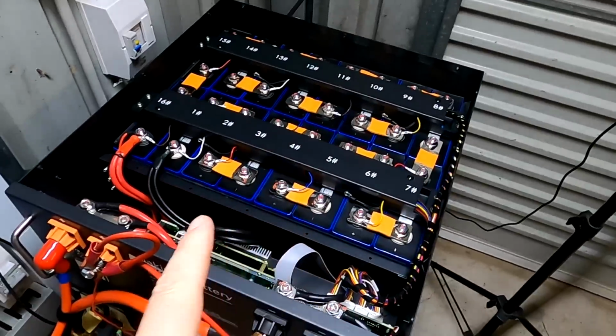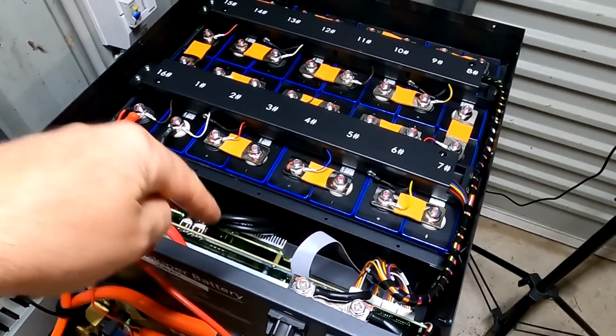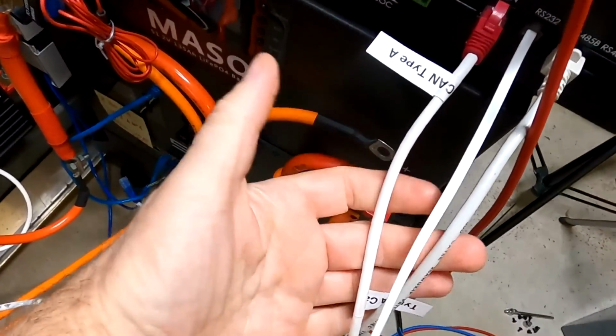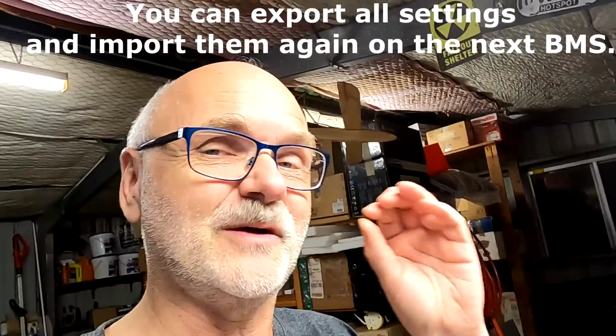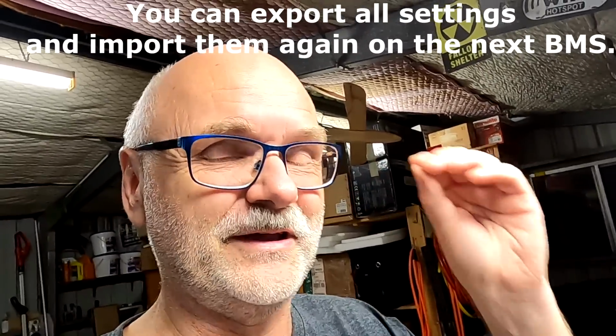So I really like the battery and the whole setup, the installation, the workmanship. This is all very good quality. But the BMS here, look at all this cabling mush here. And to access the battery with RS485, you have to set the dip switch all to 0 again. So you could say, well, then you use RS232, right? Exactly, you can. But if you have like 5 of these batteries and you want to change one parameter, you have to change your cable from one battery to another and change your parameters and settings individually for each battery.